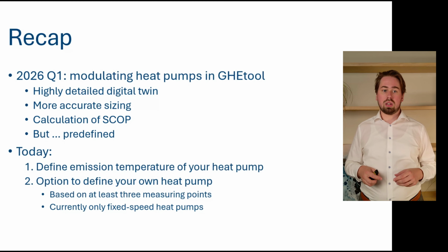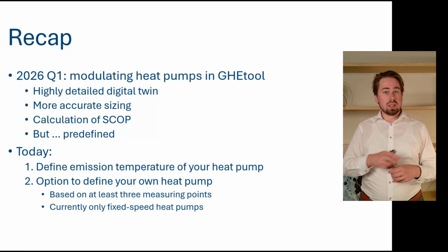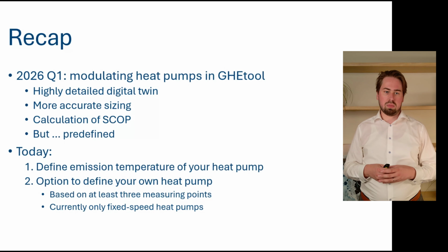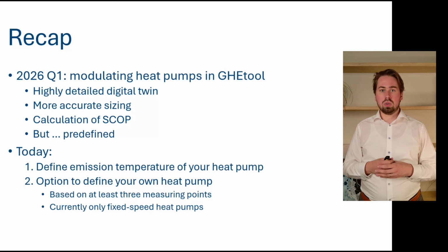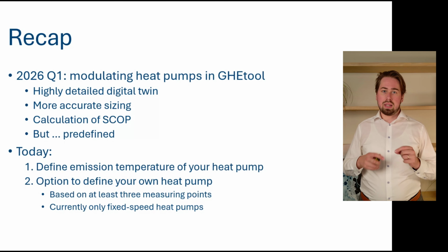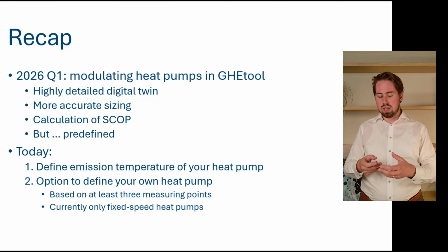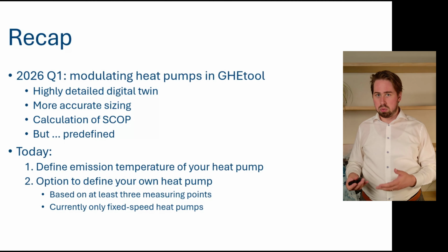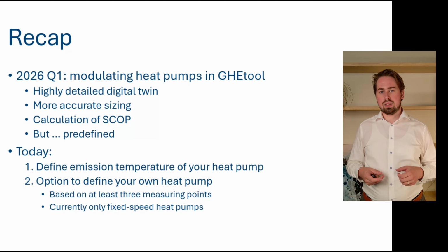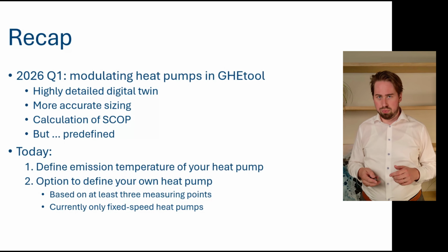And secondly, what we will be talking about is a way to define your own heat pump. And we found a way that you do not need 80 measurement points for this, but only 3, which is typically given in the datasheet of some sort. Now, one note at this moment is that this methodology will only work for fixed speed heat pumps at the moment, because modeling the part load behavior, like we did in February with the manufacturers we collaborate with, is not that easy and straightforward. However, we will be continuing researching this topic as well in order to find also a simplified methodology for that. And once we do, we will also implement it in the software.